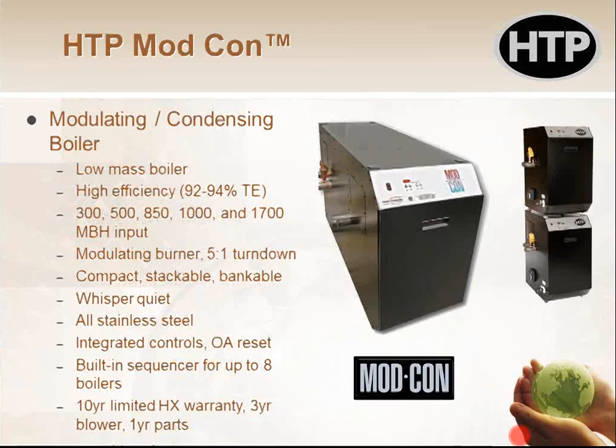And the big brother in that series, and then we'll move on to some other stuff here, is the ModCon. It's a modulating condensing boiler. It used to be 300, 500, and 850,000 BTUs. You could stack them like it shows in the picture over there. And now for the 1 million and 1.7 million BTU sizes, you can get them pre-stacked at the factory with a pre-manufactured manifolding kit and a manifolding kit for the PVC side as well. So you only have one vent going up. I believe it's an 8-inch vent.